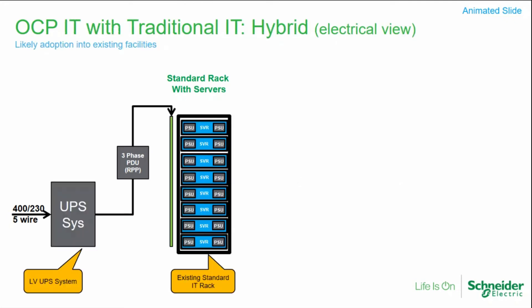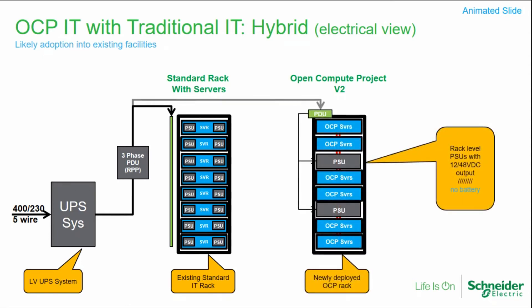When you look at this, you have to wonder if it's for everybody. If you have a data center with mixed loads — traditional servers with an upstream UPS system — you can deploy open compute right next to those racks, just without batteries inside the rack, which is what some enterprises already do. One open compute member like Fidelity who deploys open compute gear does it that way — the centralized UPS is there to support both OCP and traditional servers.